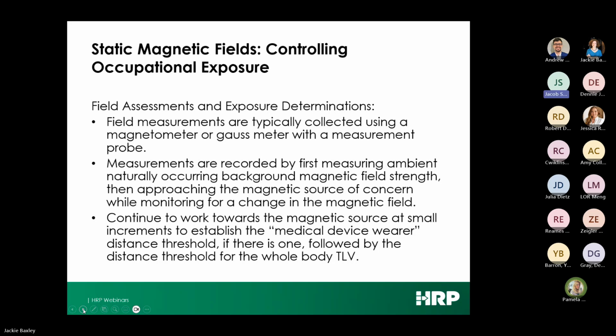For field assessment and exposure determination, if we know we're getting a magnetic component in, it's a good idea, even with manufacturer specifications, to take field measurements for confirmation, just to make sure the part that arrived is actually the same one we have the cut sheet or specification for. Field measurements are typically collected using a magnetometer or a Gauss meter with a measurement probe.